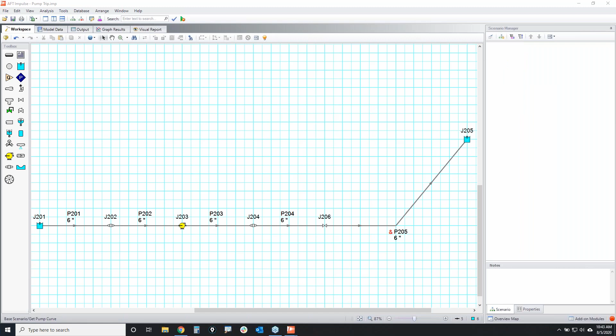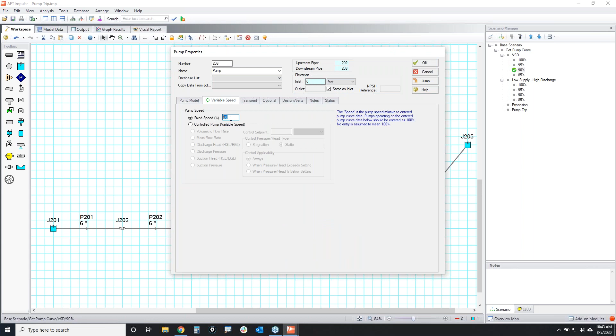Initially, I didn't have a pump curve, so I just used a fixed flow rate value as an assumption. And then once I figured out that the 6-inch diameter piping is what I needed, and I knew what the supply tank height was, I was able to get a pump curve for my pump. Well, this is operating at 100% speed. Obviously, that's not how it's going to operate at all times. There might be situations where I want to operate my pump at different speeds. And so that first family of scenarios right here is where I'm changing the pump speed from 100% down to 85%.